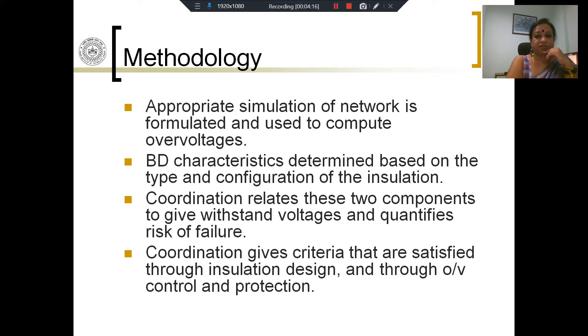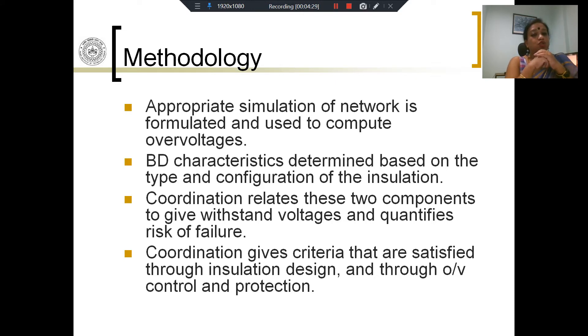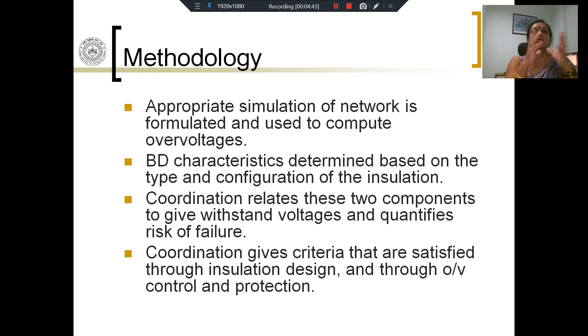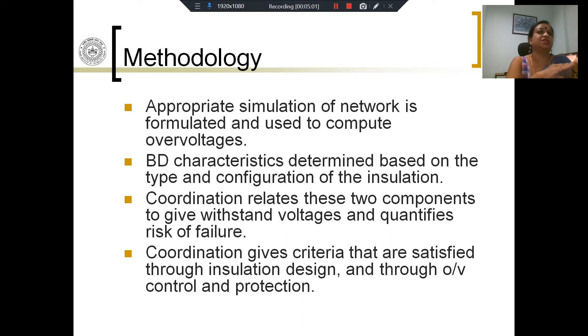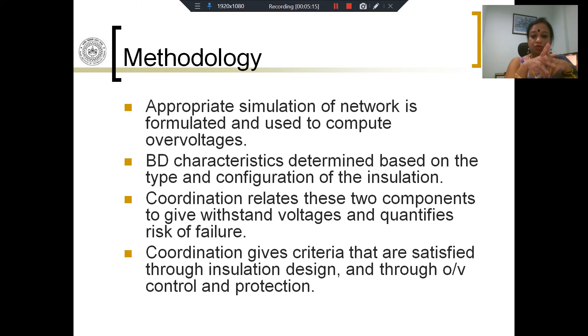To figure out what the overvoltages are, you need a model — a simulation of the entire transmission network or the apparatus of interest — and use that computer simulation to formulate the interconnection between the various parts of the network and compute the overvoltages. This aspect is not part of this course; it is covered in power system modeling. That gives us the overvoltages. The next aspect is the breakdown characteristics, which we determine depending upon the type of insulation used — for example, whether it is self-restoring or not — and the configuration of the insulation.